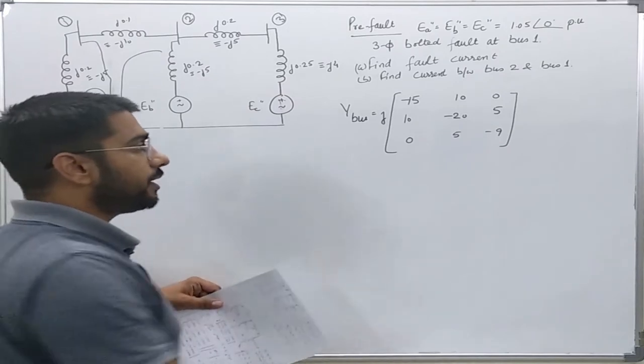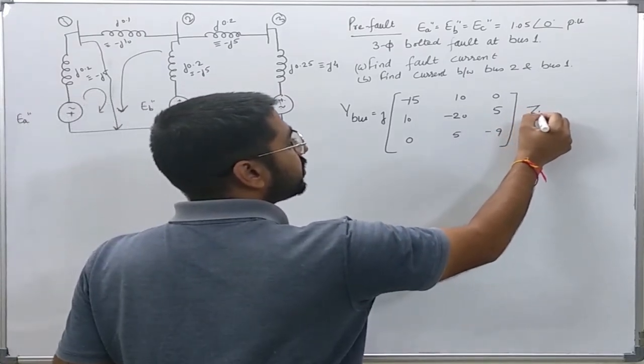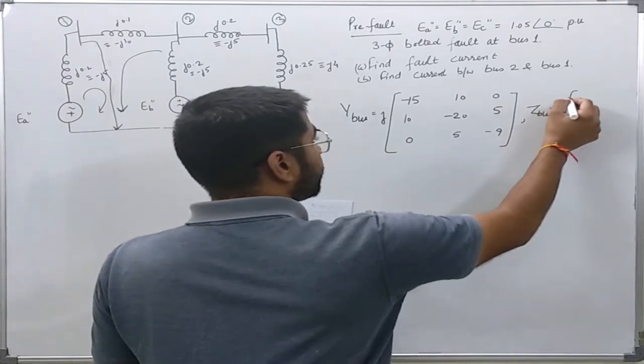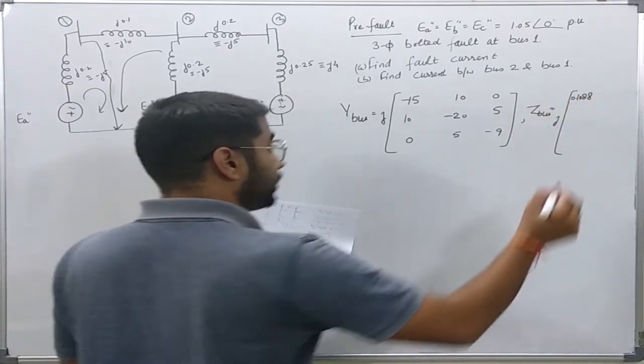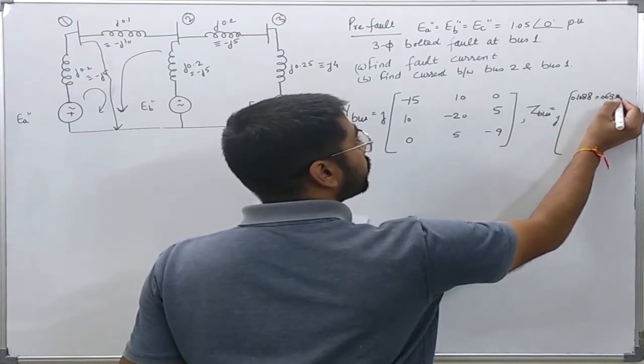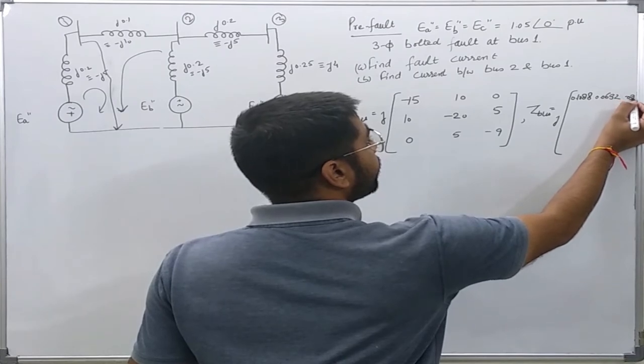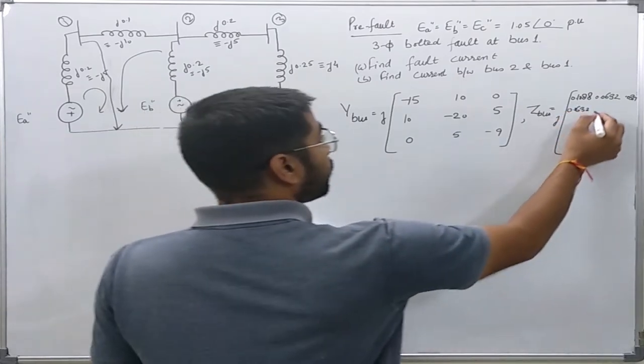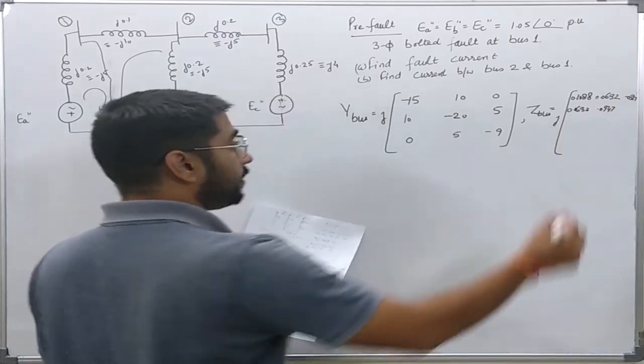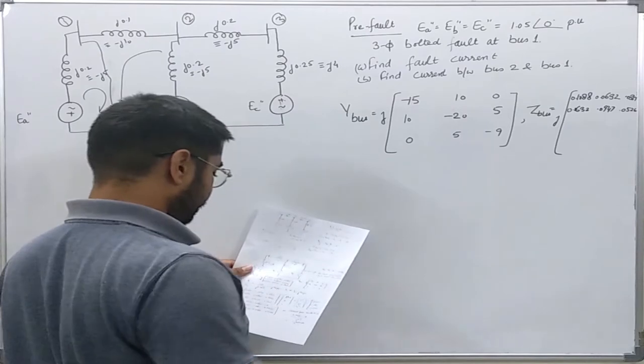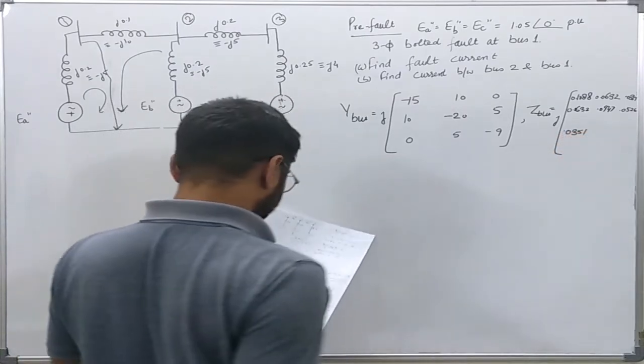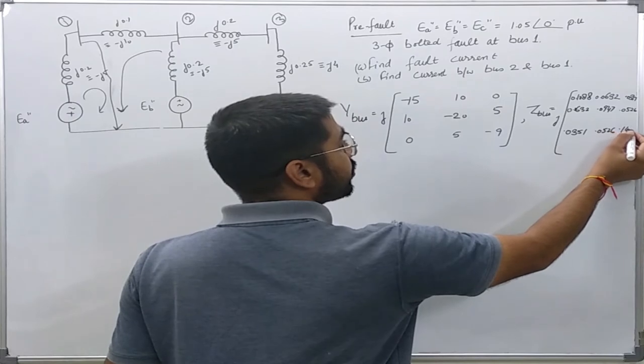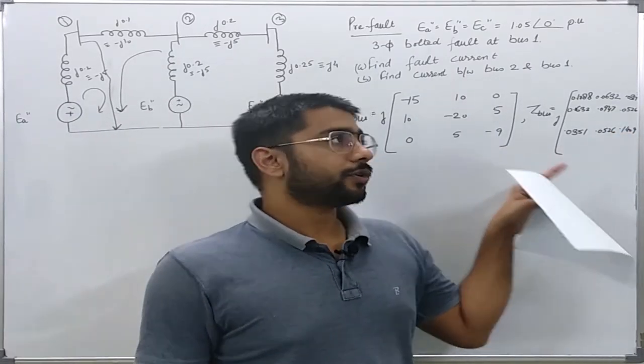Using the calculator, I have already inverted this. So Z_bus will be inverse of this, and it comes out to be, j is outside: 0.1088, 0.0632, 0.0351, 0.0632, 0.0947, 0.0526, 0.0351, 0.0526, 0.1409. So this is the bus impedance matrix for the given network.